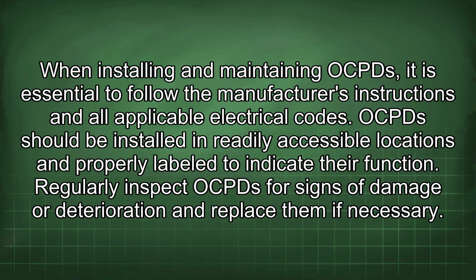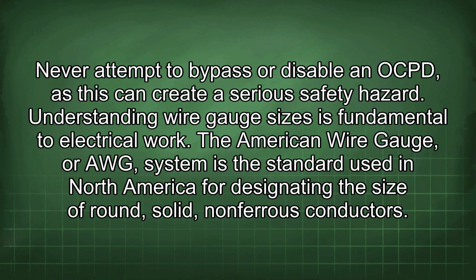When installing and maintaining OCPDs, it is essential to follow the manufacturer's instructions and all applicable electrical codes. OCPDs should be installed in readily accessible locations and properly labeled to indicate their function. Regularly inspect OCPDs for signs of damage or deterioration and replace them if necessary. Never attempt to bypass or disable an OCPD, as this can create a serious safety hazard.